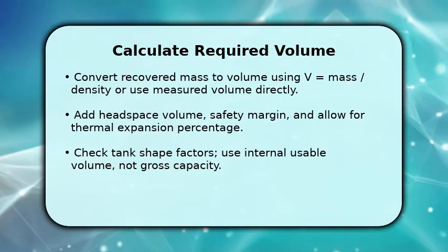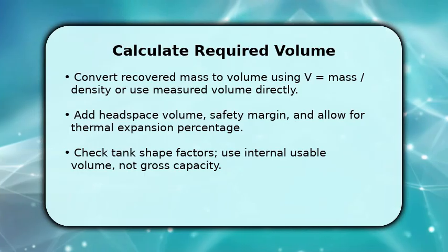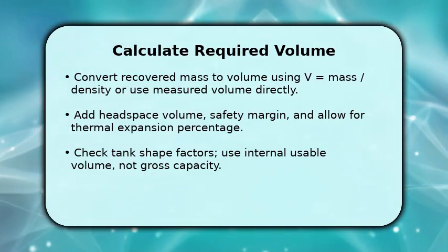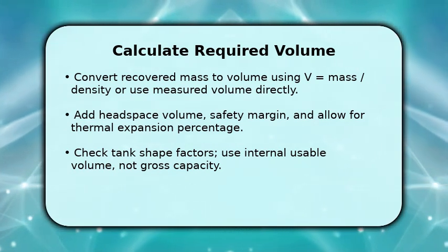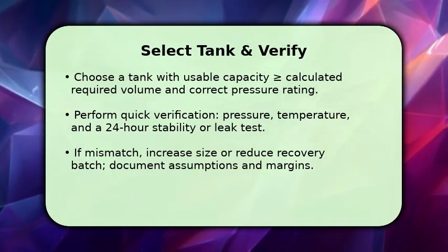it. Finally, adjust for the tank's usable volume. Remember fittings, baffles, and internal structures reduce usable volume. So use manufacturer usable capacity.